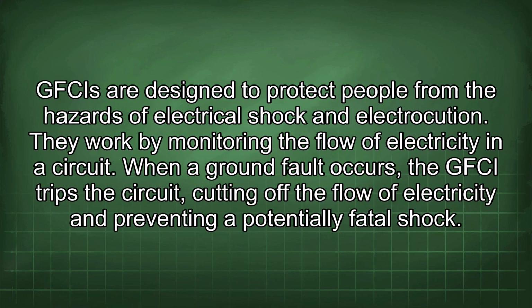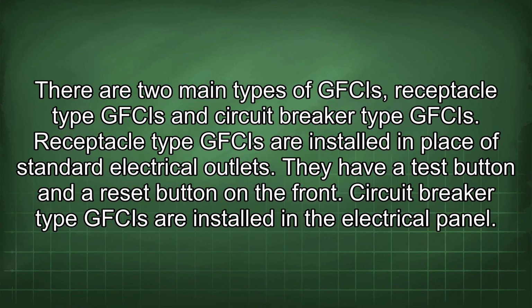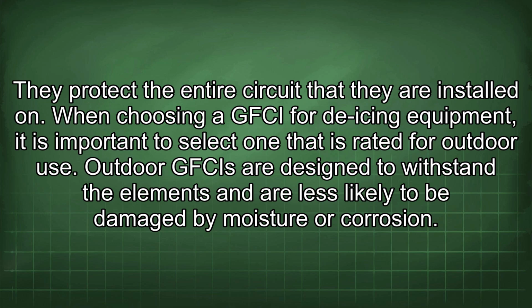GFCIs are designed to protect people from the hazards of electrical shock and electrocution. They work by monitoring the flow of electricity in a circuit. When a ground fault occurs, the GFCI trips the circuit, cutting off the flow of electricity and preventing a potentially fatal shock. There are two main types of GFCIs: receptacle type GFCIs and circuit breaker type GFCIs. Receptacle type GFCIs are installed in place of standard electrical outlets. They have a test button and a reset button on the front. Circuit breaker type GFCIs are installed in the electrical panel. They protect the entire circuit that they are installed on.